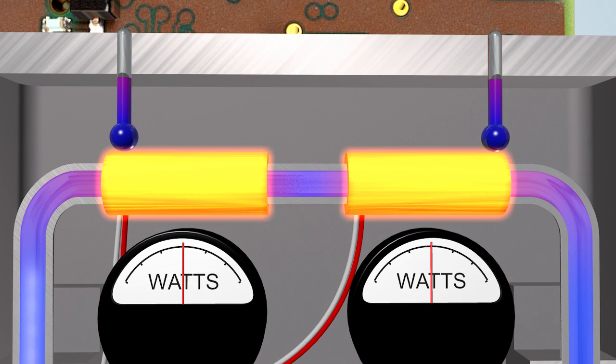The resistance of the laminar flow element ensures that a small portion of the flow is fed to the sensor. This cold gas cools the first sensor winding. In order to maintain a constant average temperature over the first winding, the power to this winding is increased to provide additional heat.